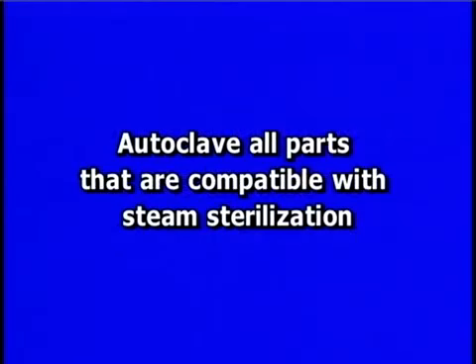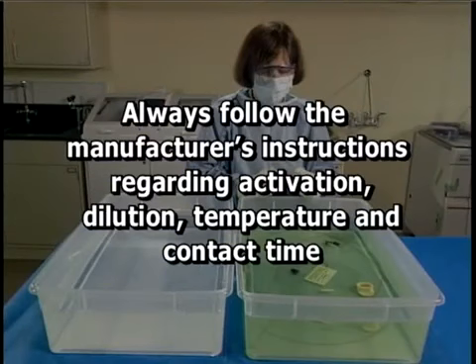Now that the parts are clean, it is highly recommended that you autoclave all parts that are compatible with steam sterilization. If you choose to high-level disinfect these components rather than sterilize them, immerse the valves, brushes, and adapters into a disinfectant solution, which has been prepared according to the manufacturer's instructions. Use a syringe to flush inside the valves and pistons. Depress and release the pistons on each valve while submerged. Ensure that disinfectant solution contacts all internal surfaces.